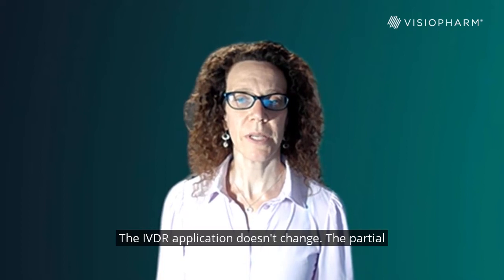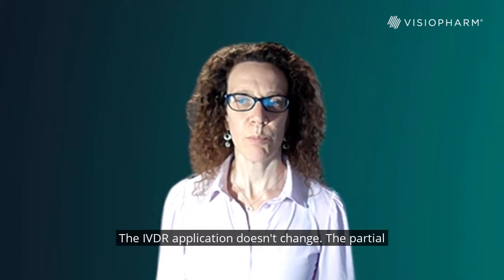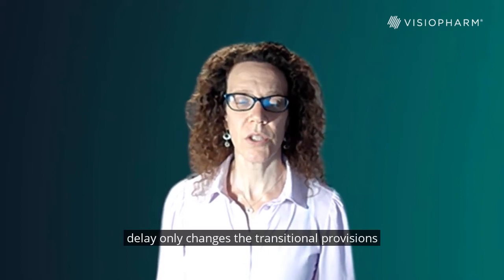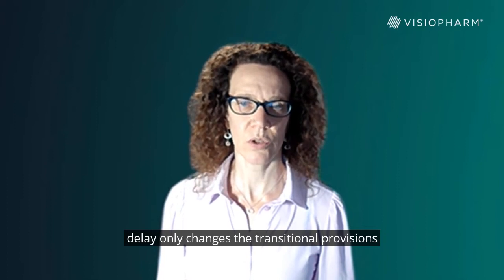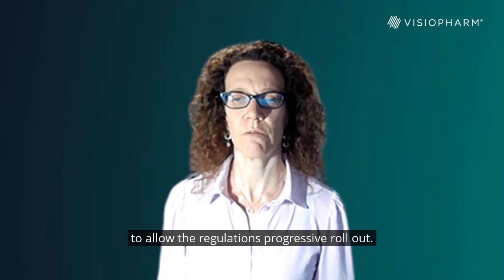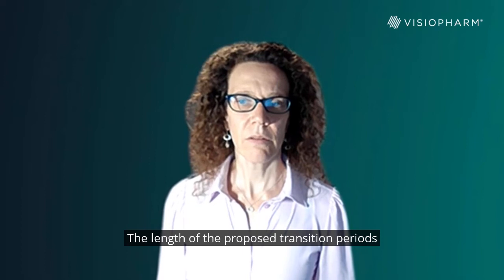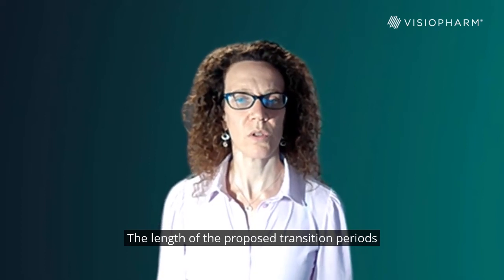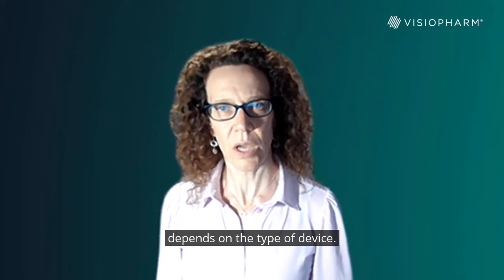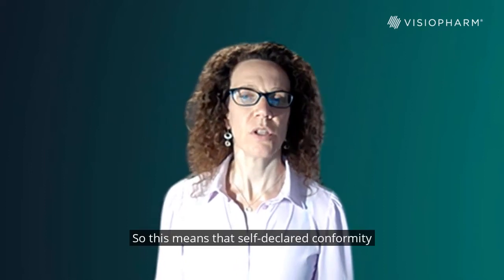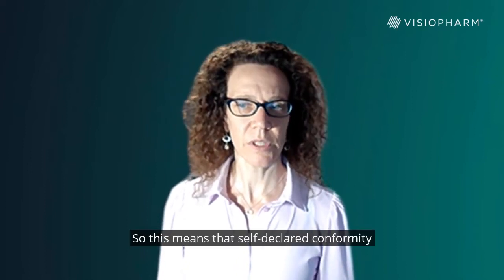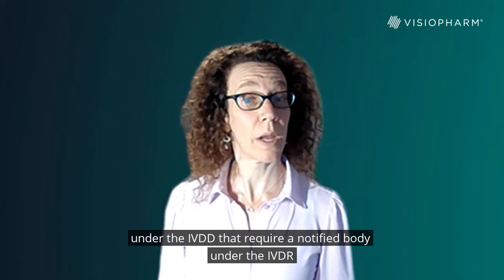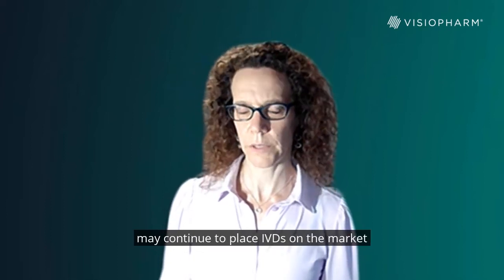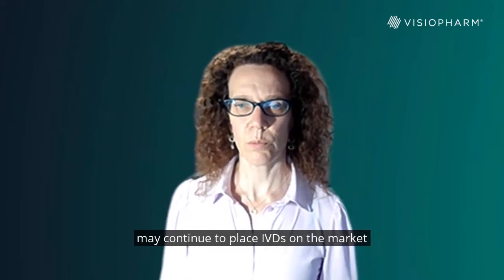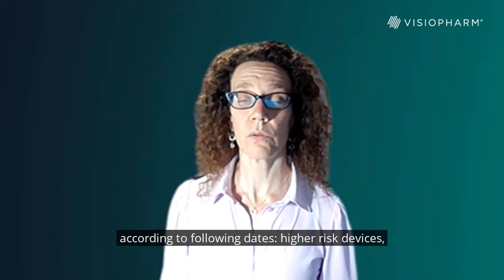The IVDR application doesn't change. The partial delay only changes the transitional provisions to allow the regulation's progressive rollout. The length of the proposed transition periods depends on the type of device. So this means that devices with self-declared conformity under the IVDD, but which require a notified body under the IVDR, may continue to be placed on the market according to the following dates.